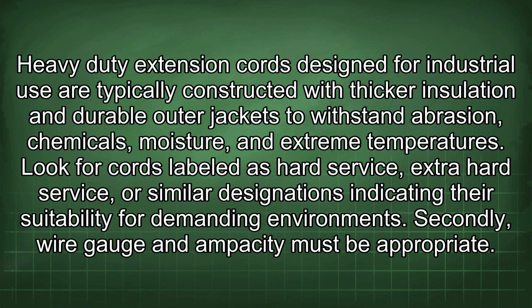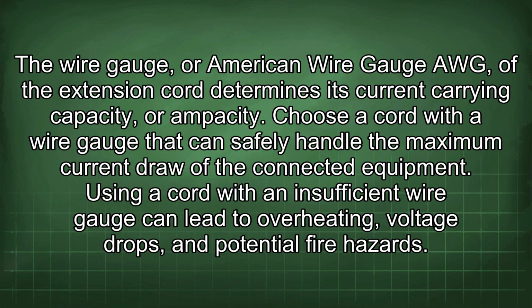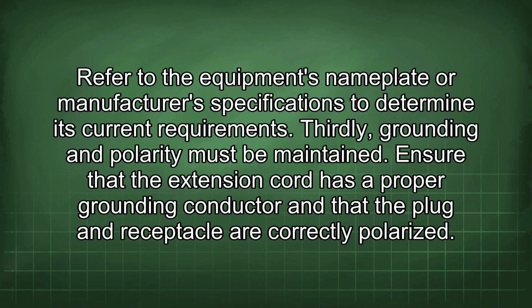Secondly, wire gauge and ampacity must be appropriate. The wire gauge, or American wire gauge AWG, of the extension cord determines its current carrying capacity, or ampacity. Choose a cord with a wire gauge that can safely handle the maximum current draw of the connected equipment. Using a cord with an insufficient wire gauge can lead to overheating, voltage drops, and potential fire hazards. Refer to the equipment's nameplate or manufacturer's specifications to determine its current requirements.